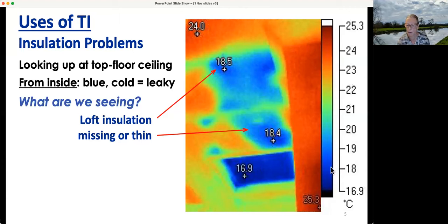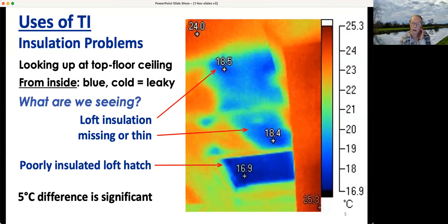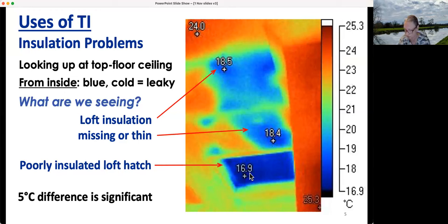You'll notice the colour scale. We tend to use the same palette: red is hot, blue and black is very cold, and greeny yellows are in the middle. The poorly insulated loft hatch reads 16.9 degrees, while the main ceiling is at 24 — that's a seven degree temperature difference, which is a lot. The missing insulation is also pretty bad. If it's just one or two degrees difference on a small area, you wouldn't worry about it.